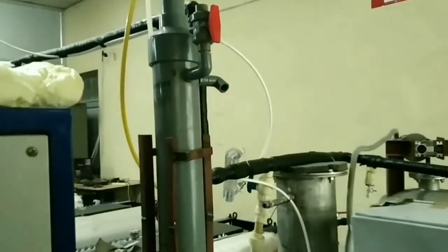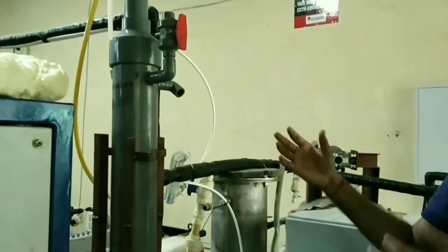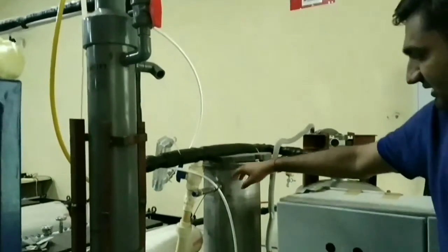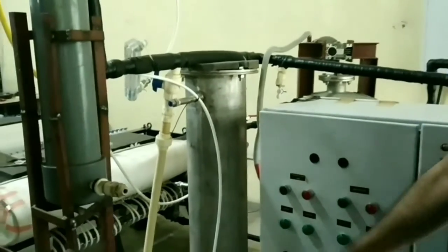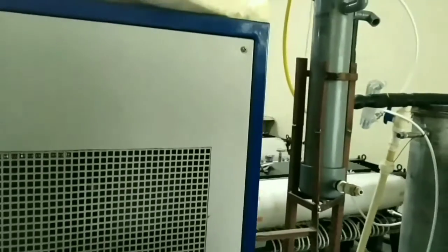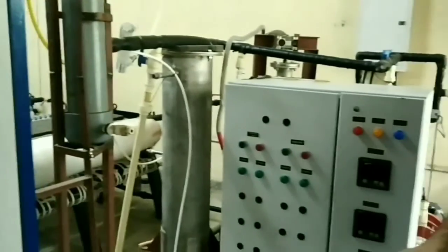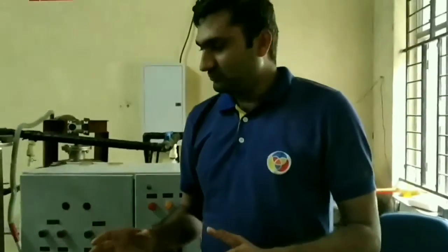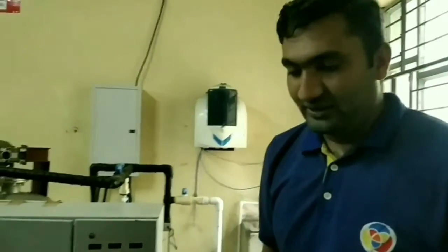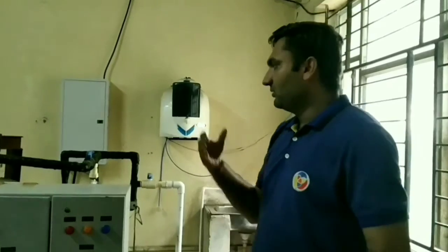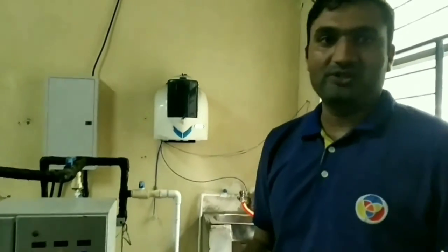On the other side we apply vacuum, and the ethanol and water vapors are condensed by this heat exchanger. The concentrated effluent we collect in this tank, and with the help of a heat exchanger we remove heat from that effluent. The concentrated effluent we send to the centrifuge, and with the help of the centrifuge we can separate the crystals of rifaximin, and the mother liquor we recirculate to the feed tank. So this is our whole process of VMD.